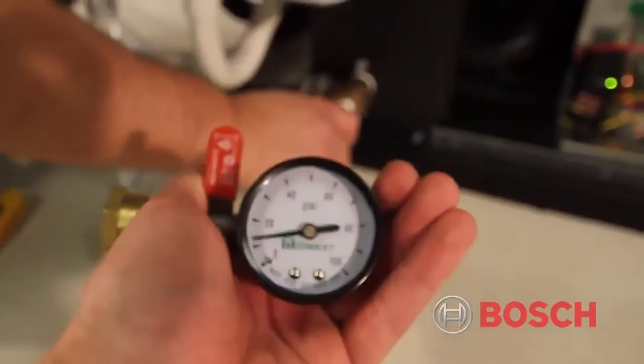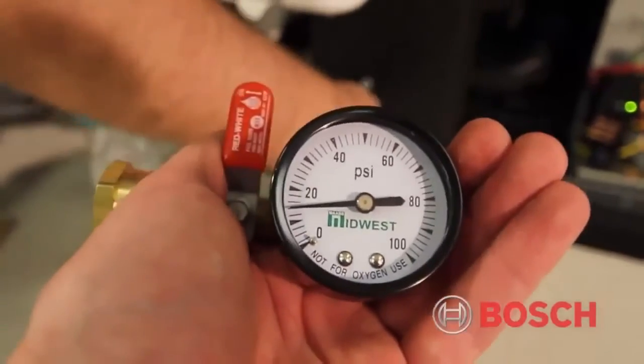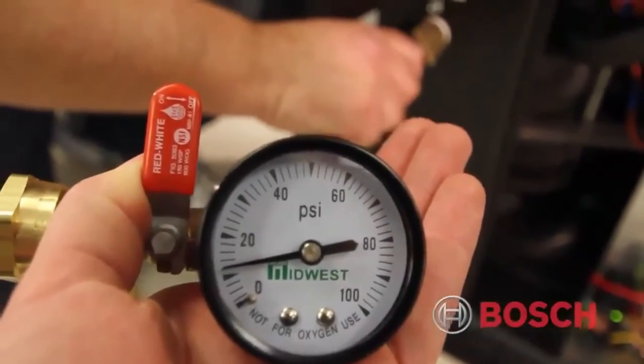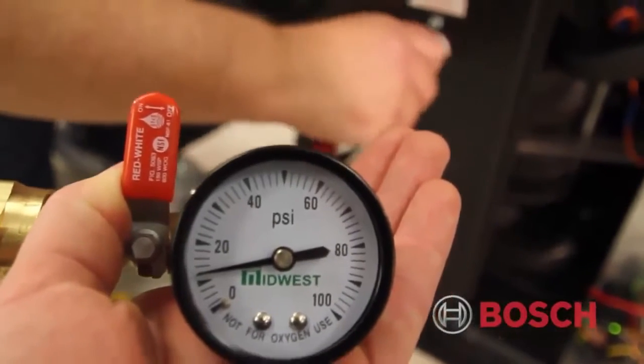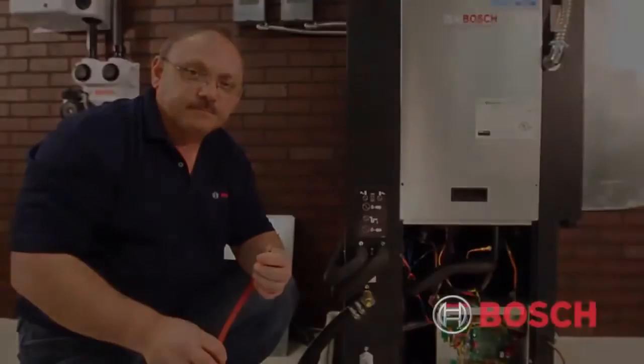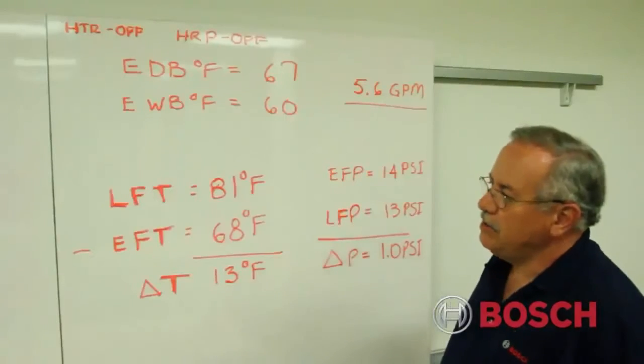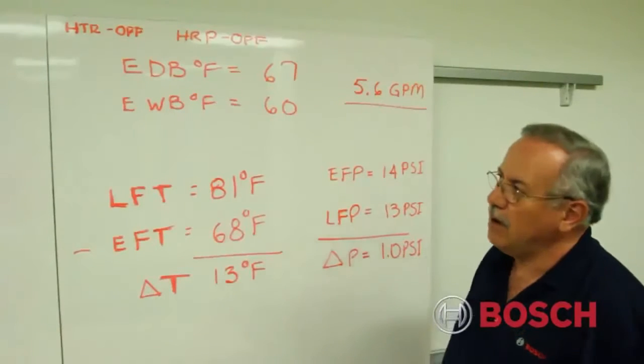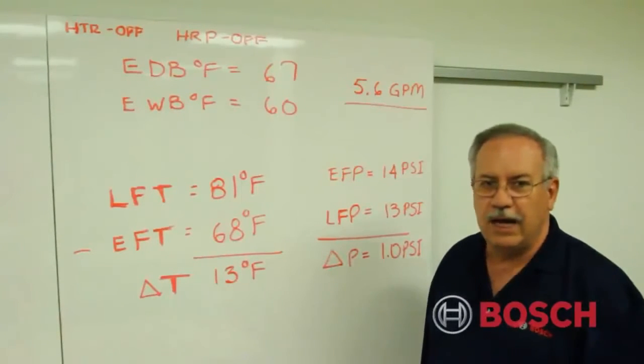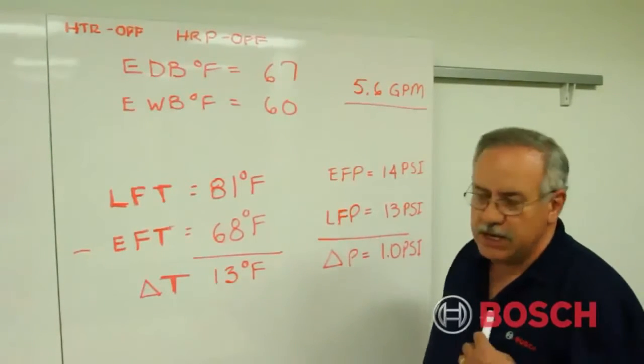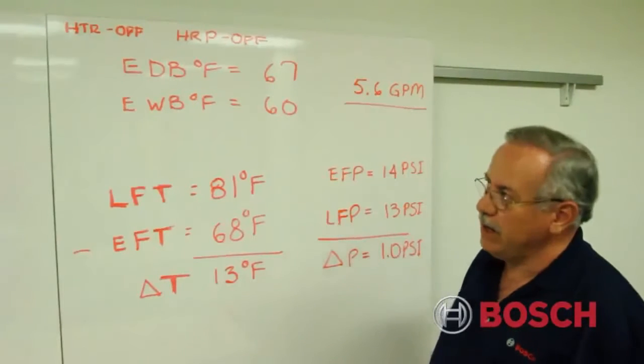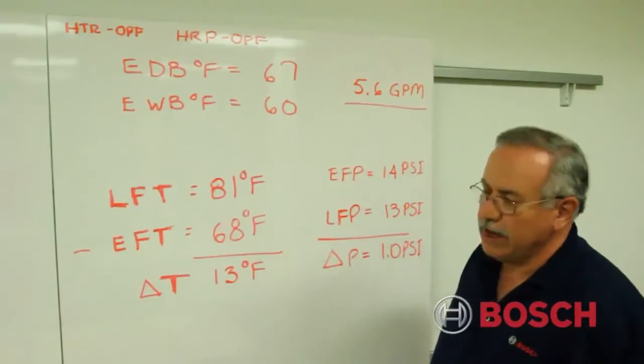We'll take a pressure measurement entering the coax and a pressure measurement leaving the coax to get our pressure drop, or our delta P, to input it into our formula. Okay, so what you've just seen is my counterpart Mark gathering data from the live machine. We're talking about a TAO25. We are operating it in cooling, so we're calculating heat of rejection.